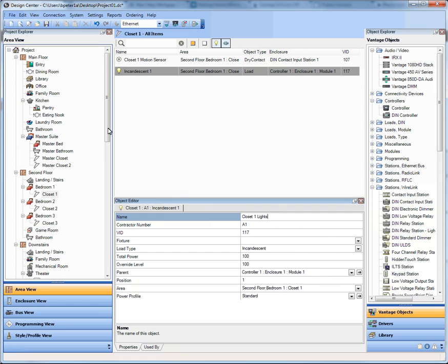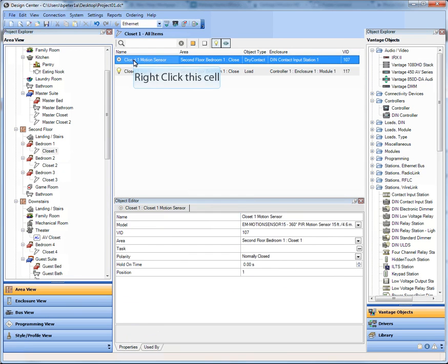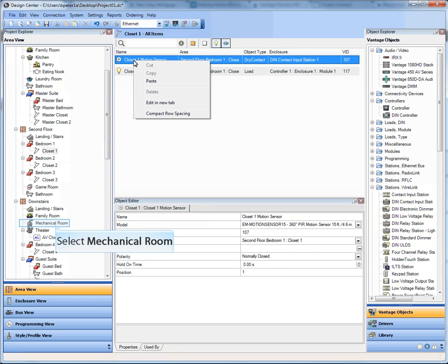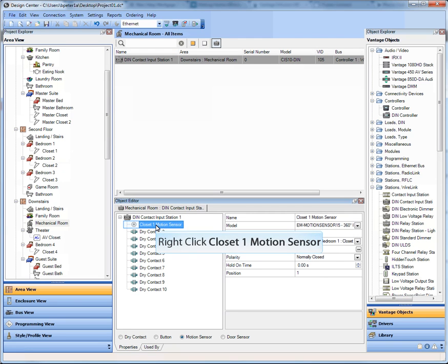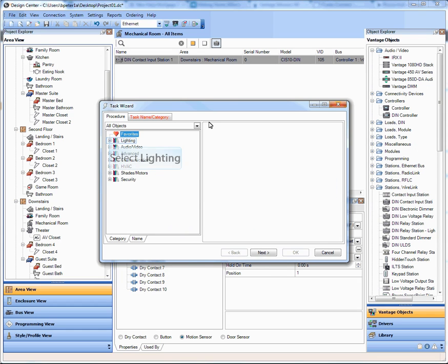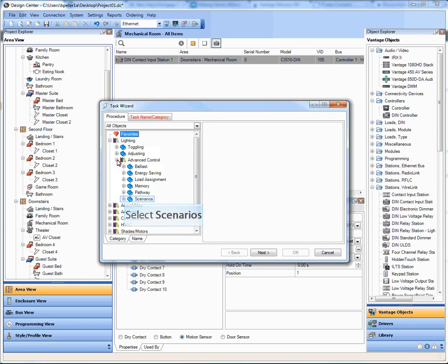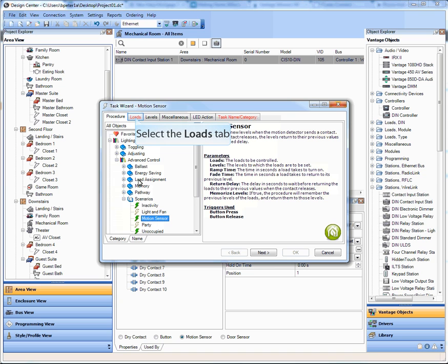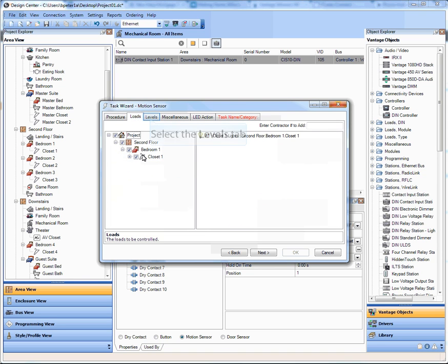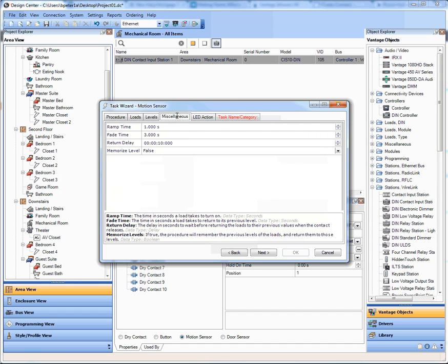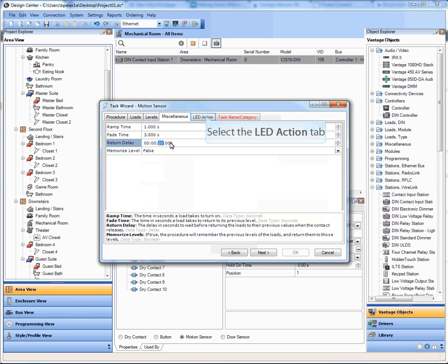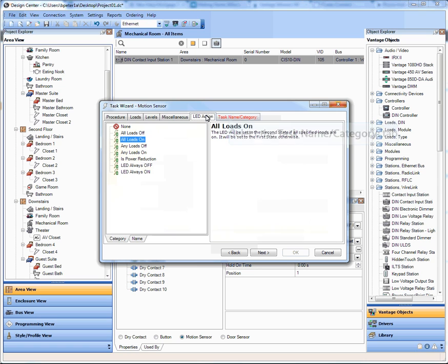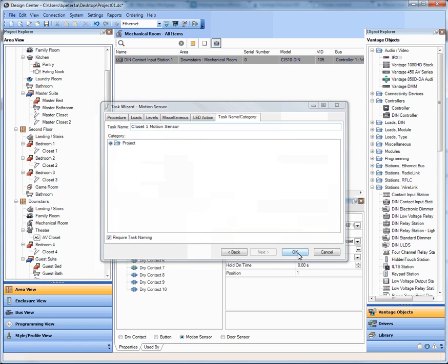And what I want to do is I want to program that contact. So what I'm going to do is go down into the mechanical room to that first closet motion sensor, right click, go to task wizard, and I'm going to pick my command in here for managing the specific motion sensor. So in that room, you can pick motion sensor, loads, pick the closet load, pick the level you want it to go to. What's the ramp time, what's the fade time, the return delay, that's how long it will be on until it stops sensing motion, and then it will turn off after that amount of time. So if you're in the closet and you leave, 10 seconds later it will turn off. You can give it an LED action and then of course a name, and we'll call this just closet one motion sensor. And voila.